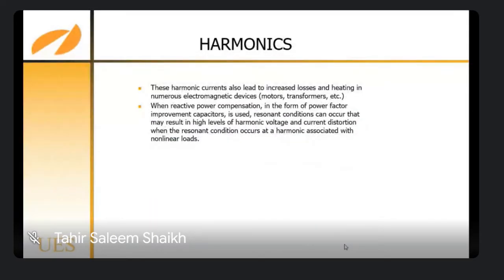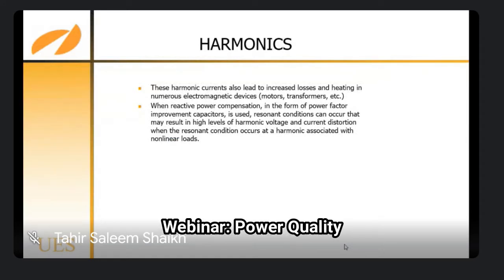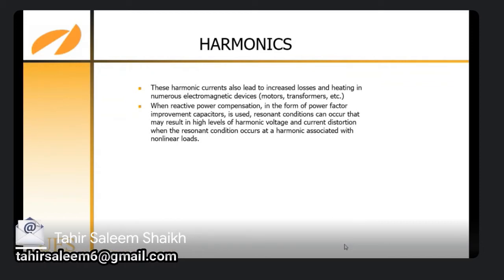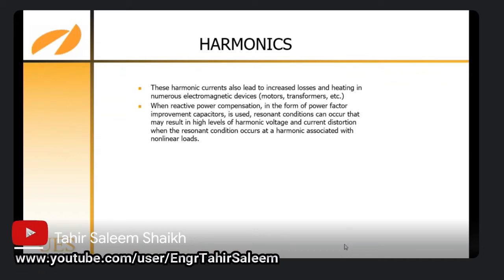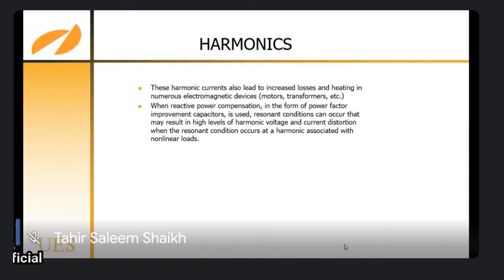These harmonic currents also lead to increased losses and heating in numerous electromagnetic devices, motors, transformers, etc. When reactive power compensation in the form of a power factor improvement capacitor is used, a resonant condition can occur that may result in high levels of harmonic voltage and current distortion.